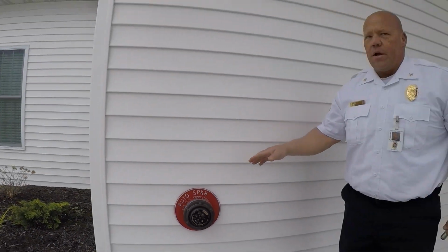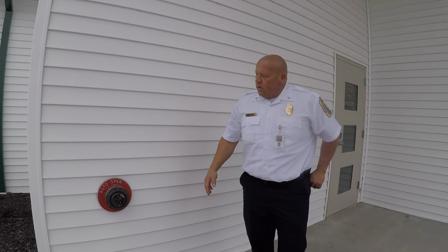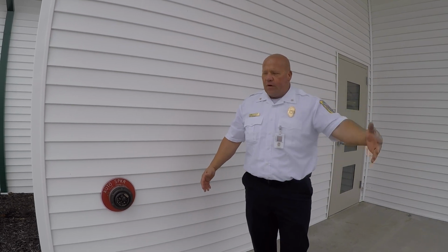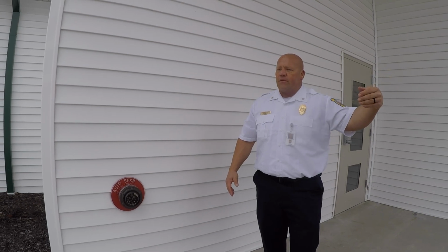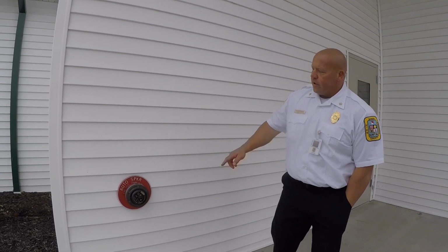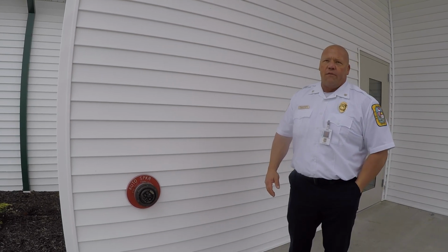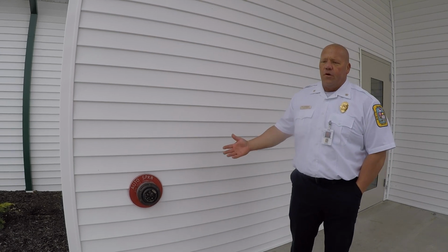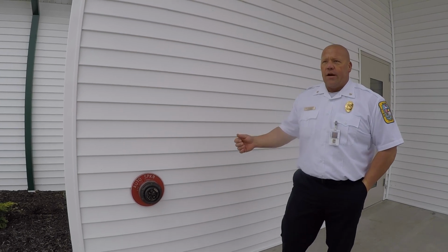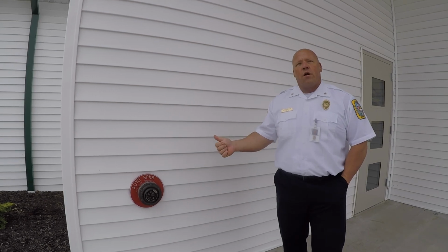Every sprinkler department connection will have a fire hydrant located within 100 feet. So this one obviously is about 10 feet away, but your supply to your engine comes from that hydrant. Your discharge then goes to your sprinkler connection to support it. Again, we're not providing the water for the sprinkler system, we're only supporting it. Two things you've got to know before you charge that line is, one, do I want to support the sprinkler system and provide more water to it?